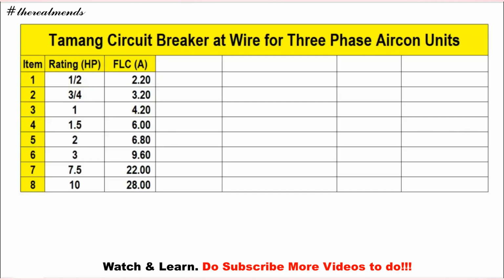After natin ma-review yung PEC, so yung ating respective aircon unit, so meron na tayong full load current. So itong mga value na to, ito yung kinuha natin dun sa table ng PEC. Okay, so 7.5, 22 amperes. Pag 10 HP, 28 amperes. So after that, kung meron ka nitong FLC, so pwede na natin makuha yung rating ng circuit breaker.